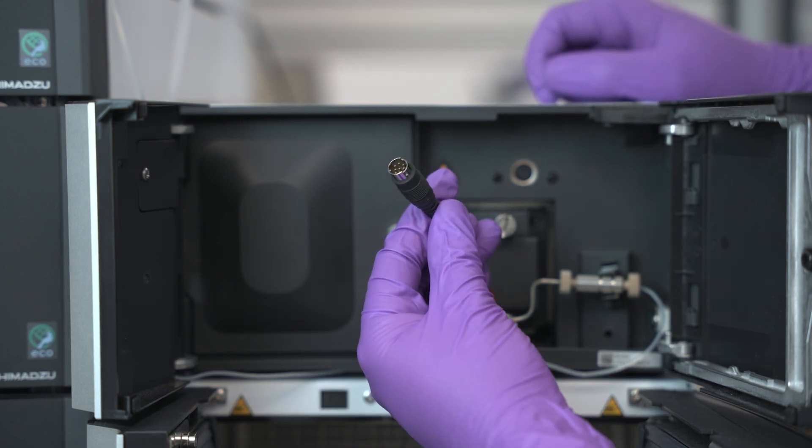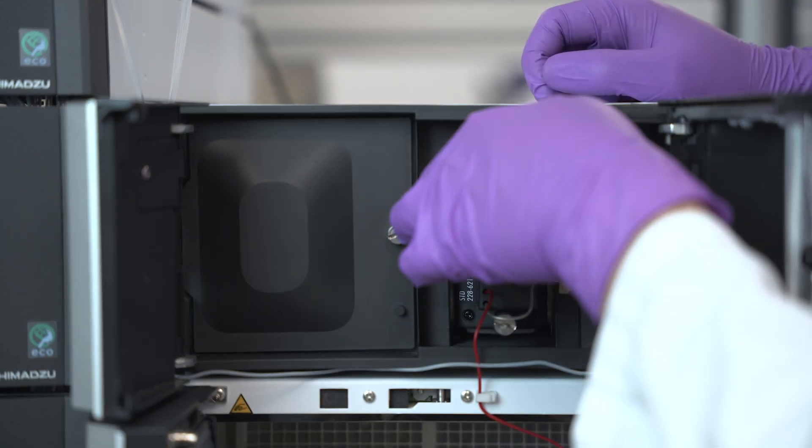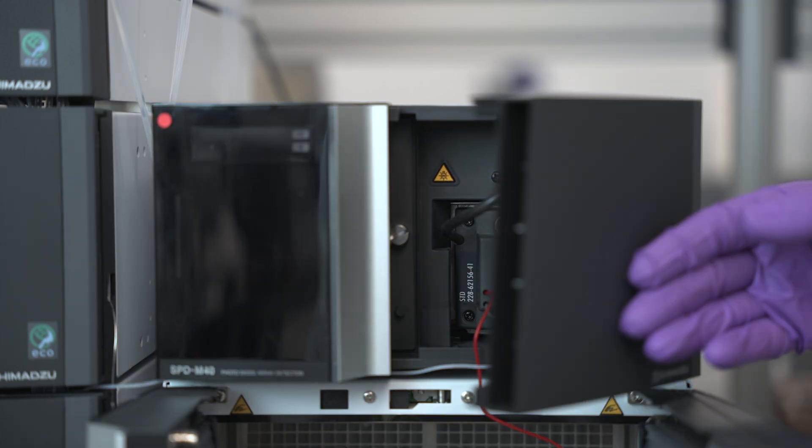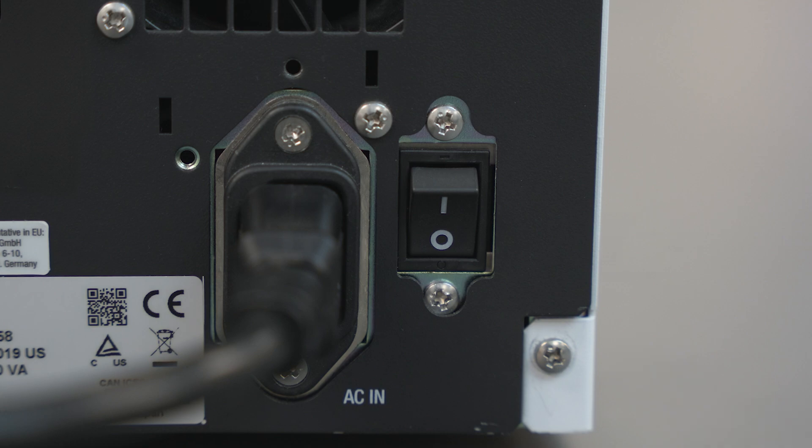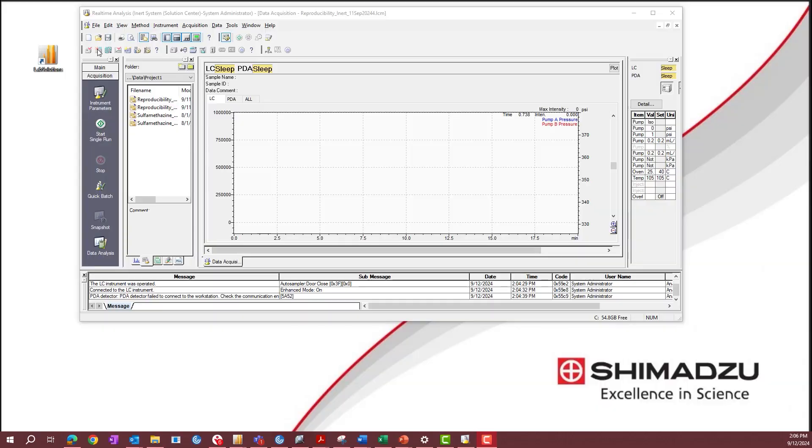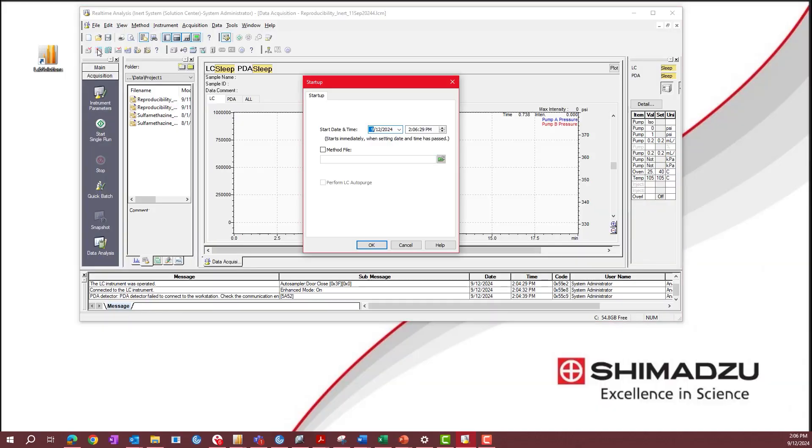Insert the connector into the instrument. Turn the detector on from the main power switch located at the back of the module. Open Lab Solutions and start up the system. Run your startup method and push out the 2-propanol from the flow cell and condition it for your analysis conditions.